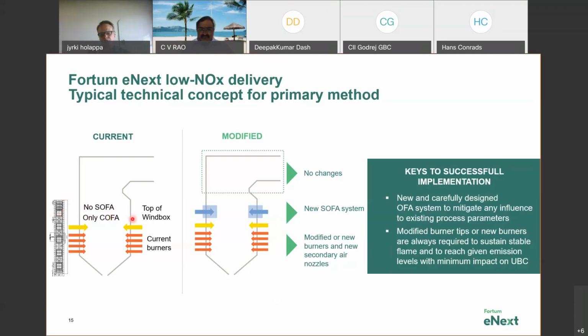In order to achieve NOx reductions efficiently while ensuring the boiler operates reliably, our concept has been that you need to not only introduce a new overfiring system, but also modify the burners. Quite often we've changed burners totally, but in India we've seen it makes more sense to modify them only, unless there's another reason to replace them. You have to consider both together to ensure the boiler works reliably, both at full load and part loads.